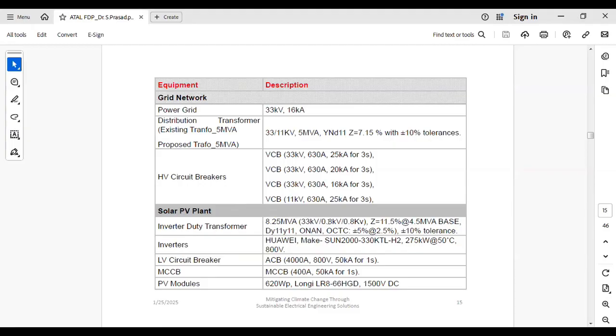So the primary side is 33 kV, the secondary side is 0.8 kV. Two LV panels, LT panels, will be there, and the voltage level is 0.8 kV. It is a 3-winding transformer, and the percentage impedance is 11.5% at 8.25 MVA base. It is a DY11, which we mostly use. The primary side is delta, the secondary side is star connected, and the OCTC will be 2.5%, 5% at 2.5% steps. That means 2 steps will be there, 2.5 into 2, 5% step changing. The percentage tolerance considered is 10%.